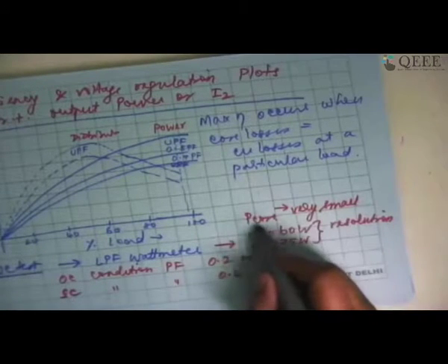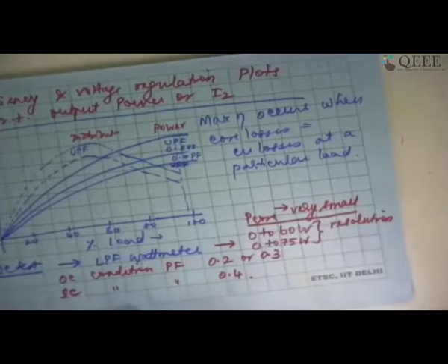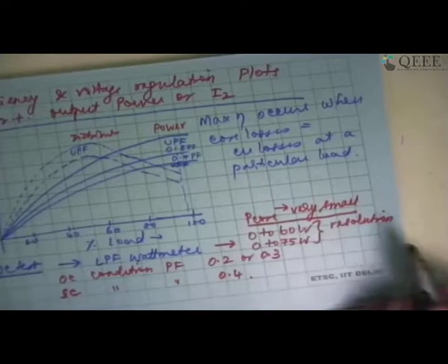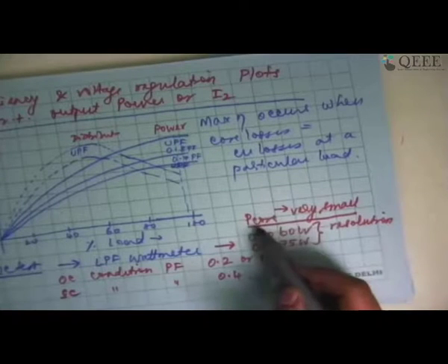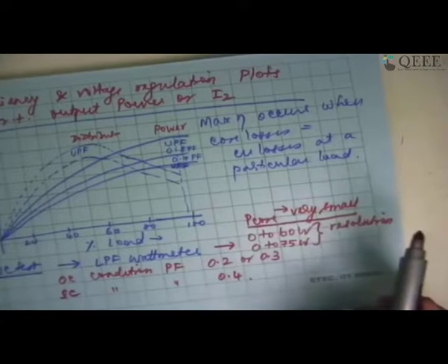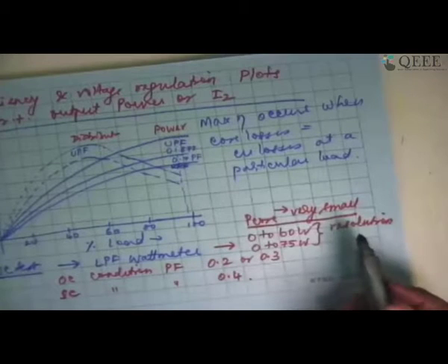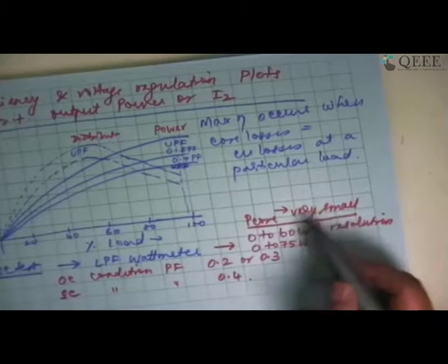So hysteresis losses and eddy current losses will be minimized. There is hardly any air gap, so everything is going to confine itself to the core. So we would normally expect that the core losses are very, very small. The magnetizing current drawn is also small. So that is the reason why we have to put a low range wattmeter.